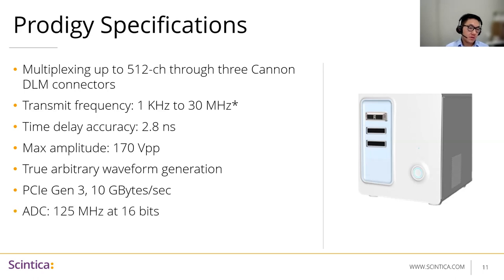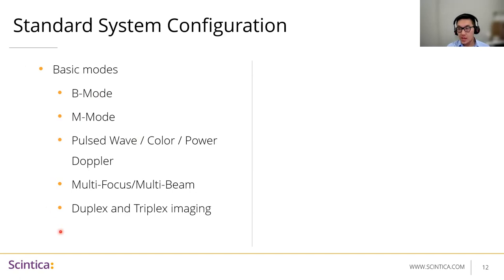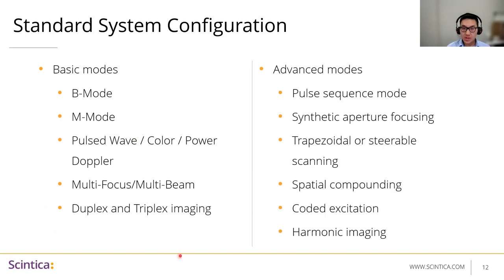The receive-side electronics has a sampling rate of up to 125 megahertz at 16 bits. The Prodigy supports a number of basic ready-to-use modes you'd expect from any ultrasound system, all included as turnkey solutions with no extra cost for any modes. These include standard B-mode, M-mode, pulse wave, color, and power Doppler, as well as multi-focus or multi-beam, and duplex and triplex imaging. In addition, there's capability for pulse sequence modes: synthetic aperture focusing, trapezoidal or steerable scanning, spatial compounding, coded excitation, or harmonic imaging.